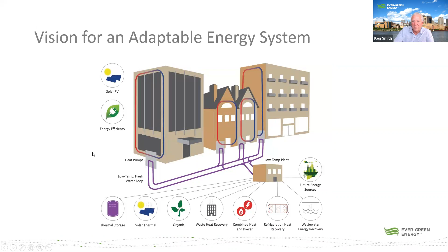In this case, when you're in summer mode and cooling the buildings, you're pulling water from the aquifer, running it through a heat pump, producing the chilled water needed for the building. There's another loop tied to the aquifer - the water from the aquifer does not enter the loop for the cooling and heating, they're actually separate. So you're utilizing the cold water for cooling, and taking the waste heat - much like a refrigerator, when you're cooling the internal part of your refrigerator, you're dumping the heat into your kitchen.